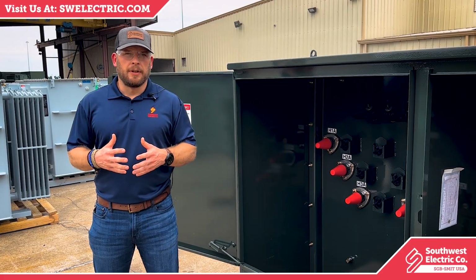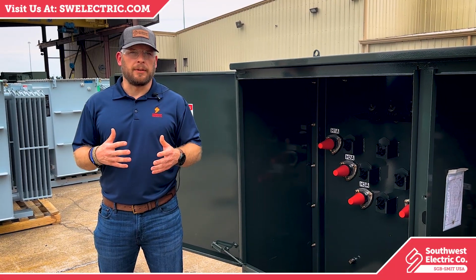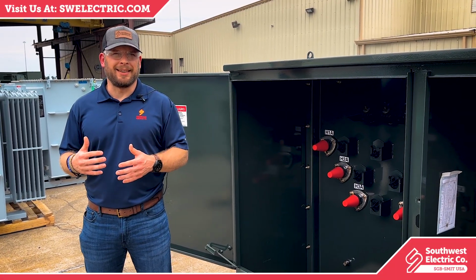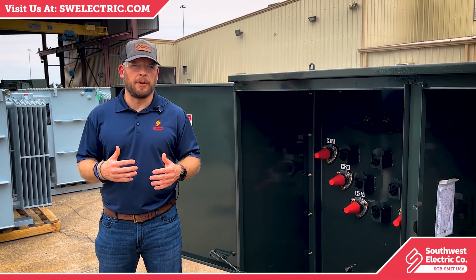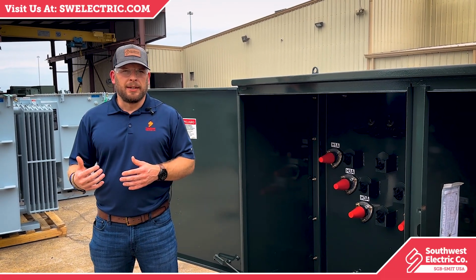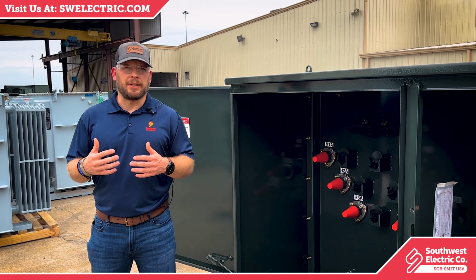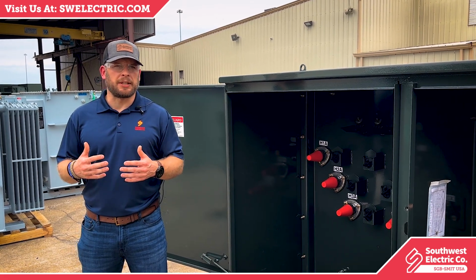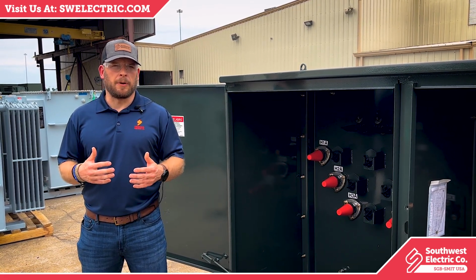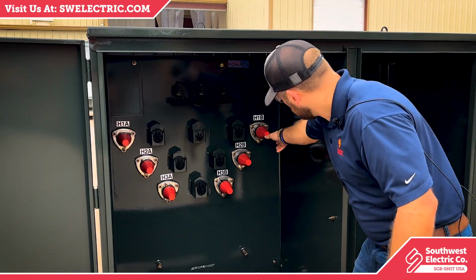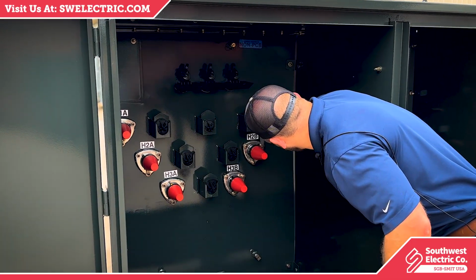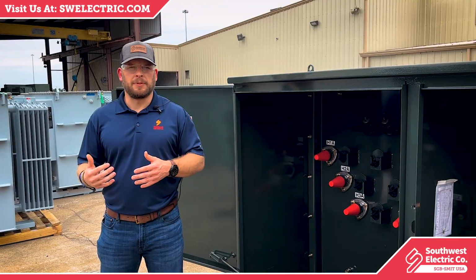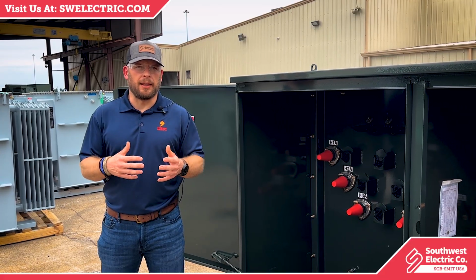The bushing fits tightly in a sealed opening of the transformer tank, which prevents leaks and protects the internal components from the environment. Inside the transformer, the bushings connect to the winding terminals using flexible leads, bus bar, or cables. Externally, the exposed end of the bushing is connected to external cables, external bus bar, or overhead lines.